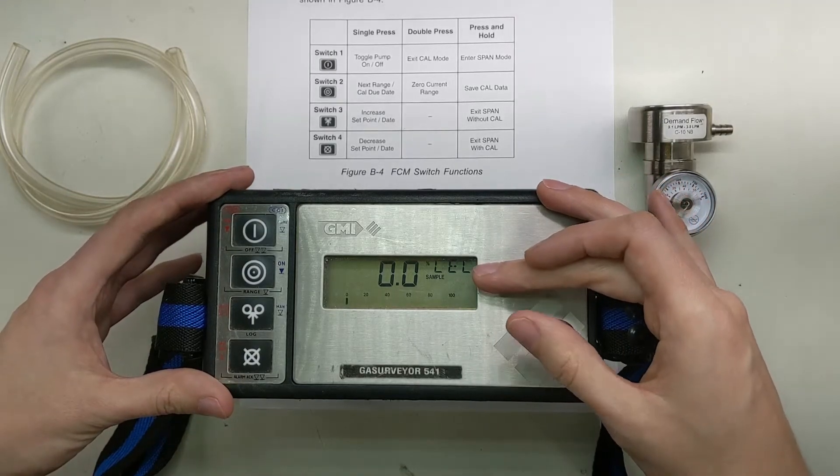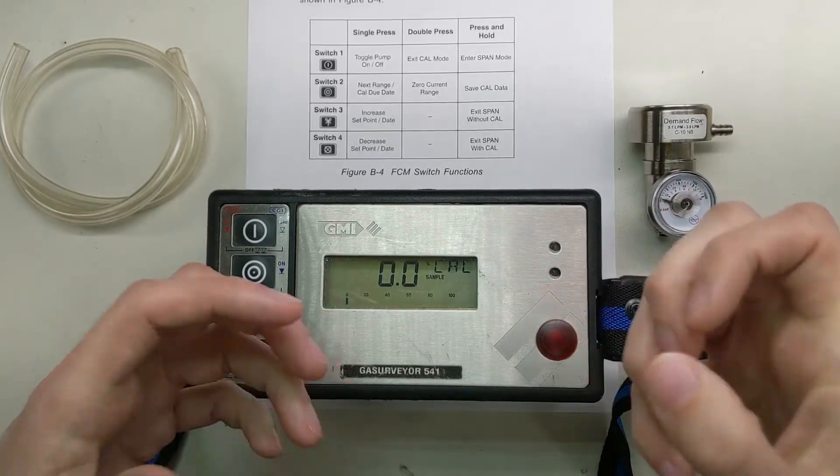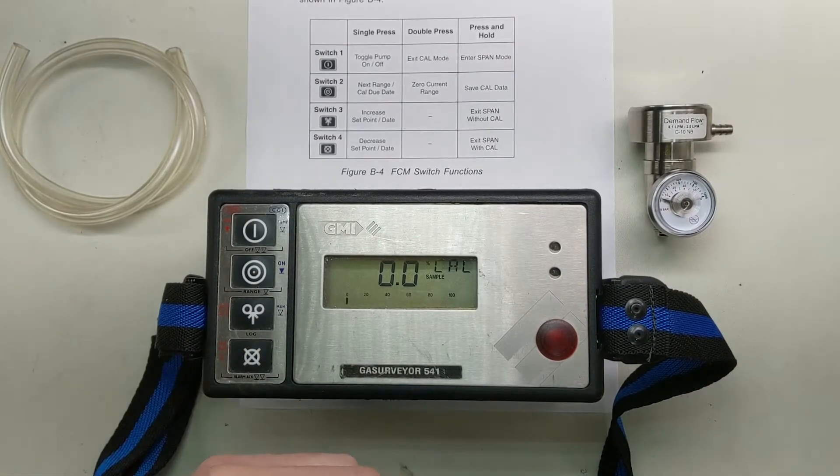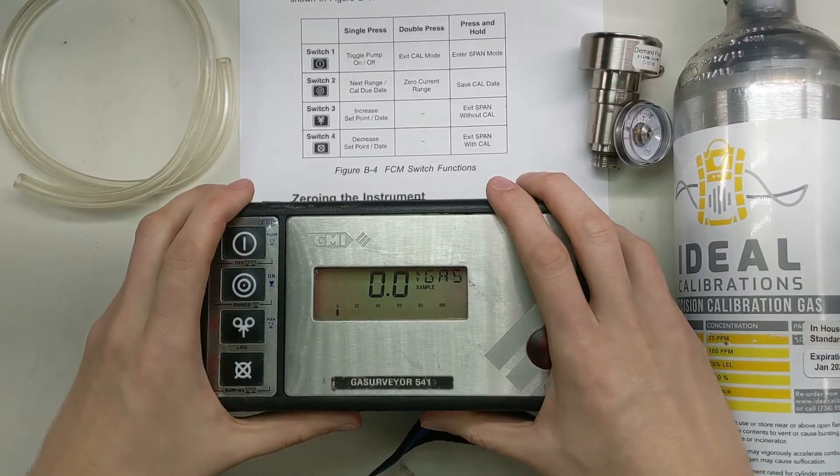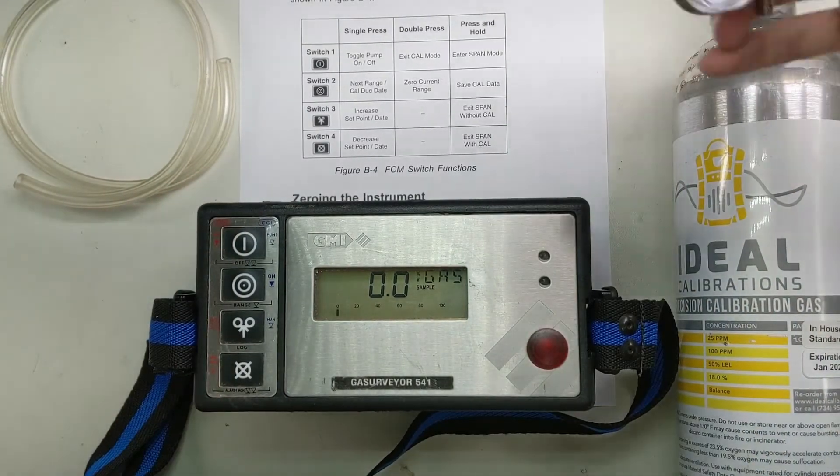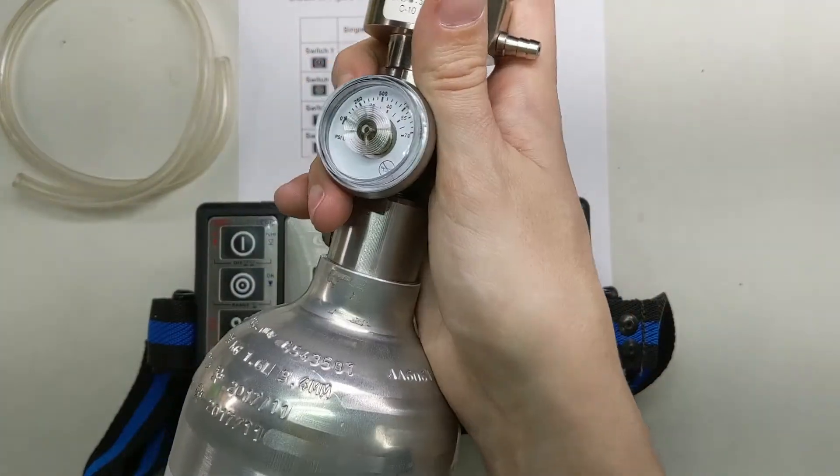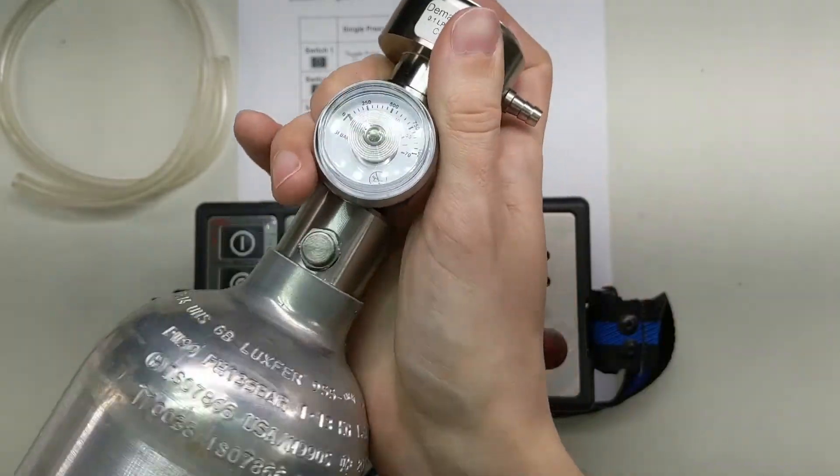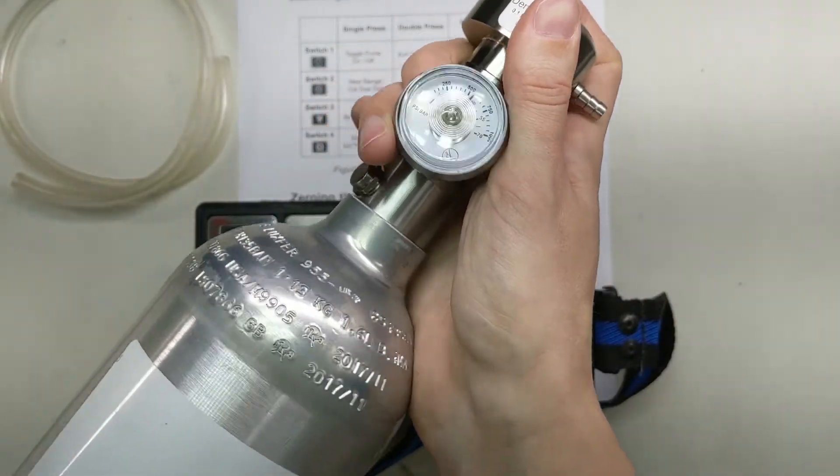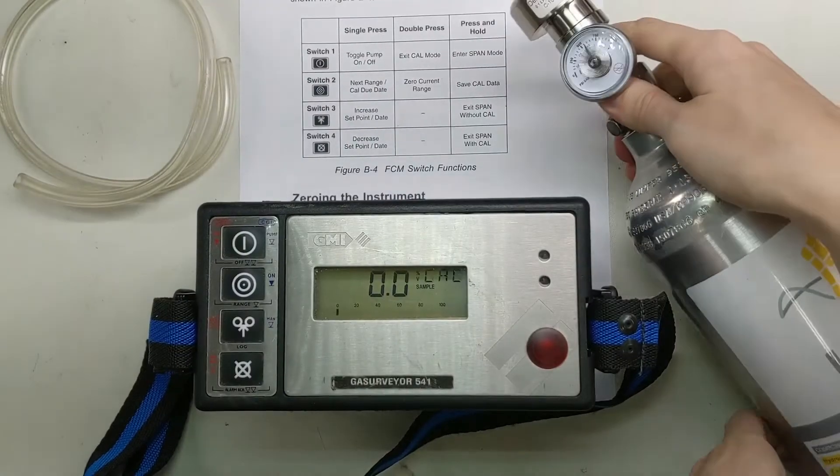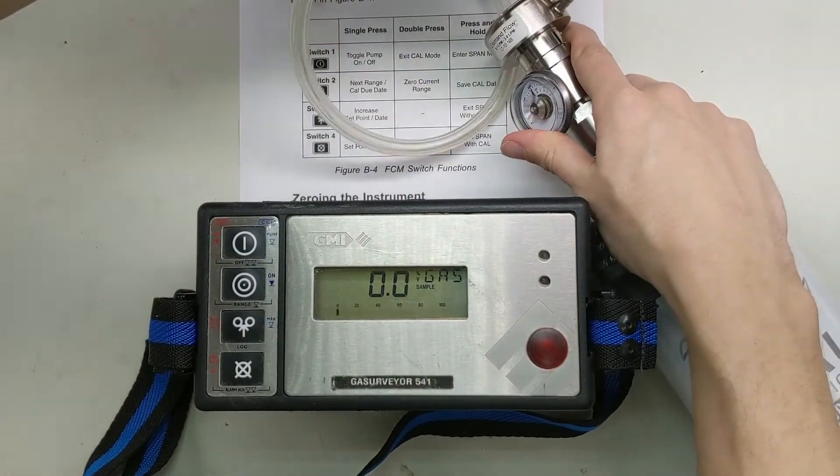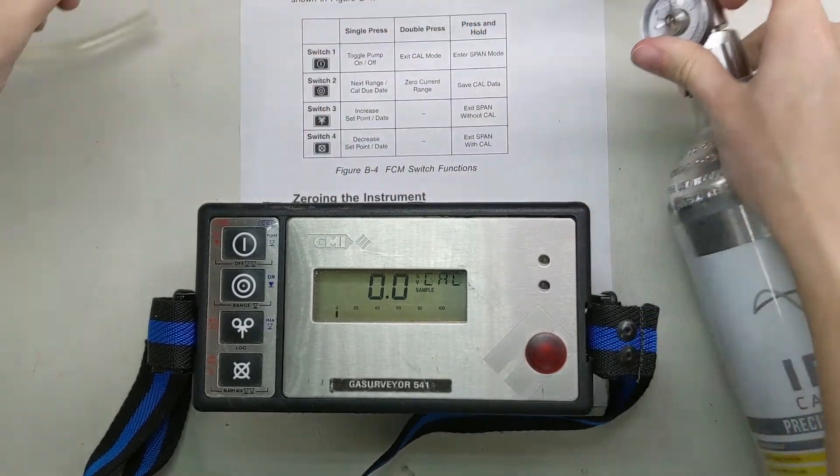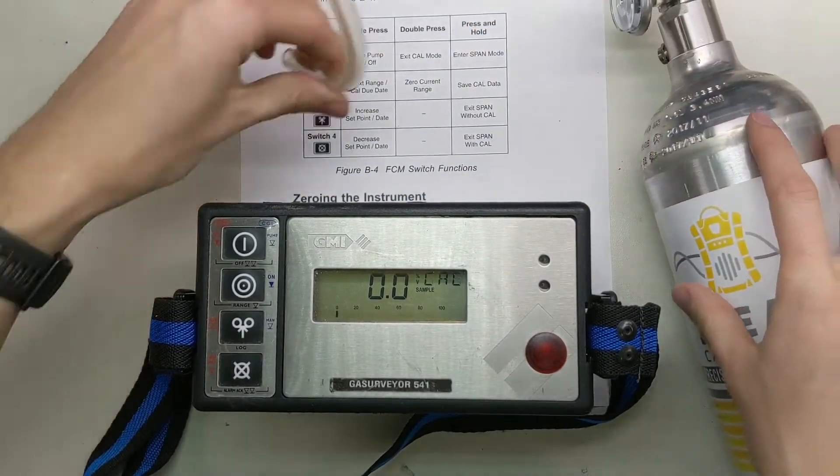Now we're back to the LEL mode. So now what we're going to do is go through and actually apply the gas cylinders to this. We're going to do our multi-gas first and then we're going to come back and do the methane. With the zero complete, we're going to grab our demand flow regulator. We're going to screw this into our cal gas cylinder. Our multi-gas cylinder is what we're going to start with. Now we grab our 3-16th of an inch tubing.